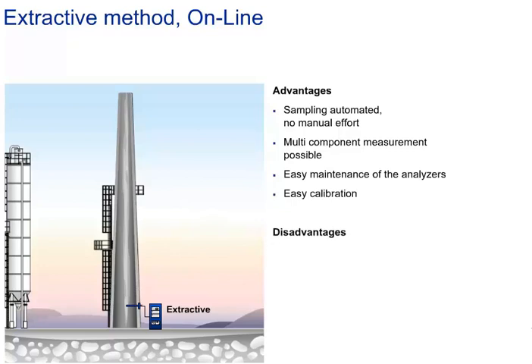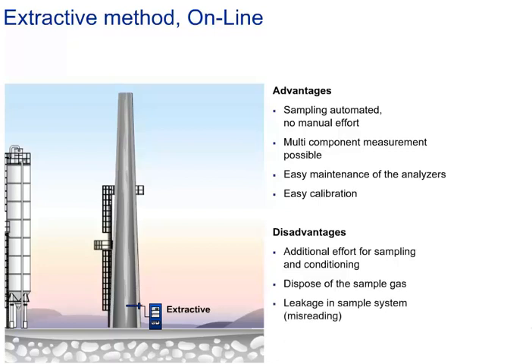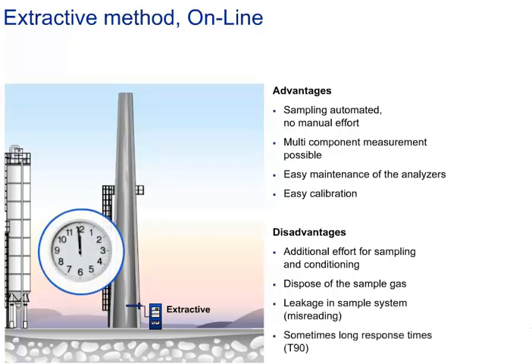Some disadvantages should also be mentioned: there is additional effort for sampling and conditioning of the sample gases; the disposal of the samples to the atmosphere after the measurement can be critical; a potential risk of leakages in the sample system can lead to misreading; and big distances to the process result in longer response times.